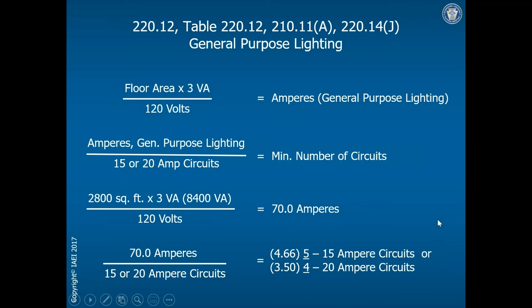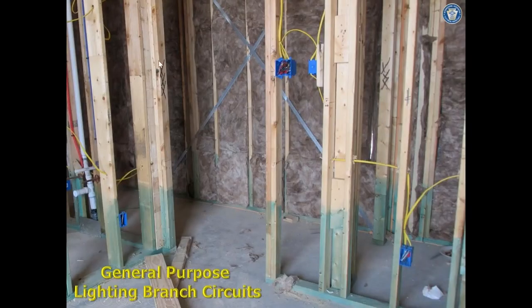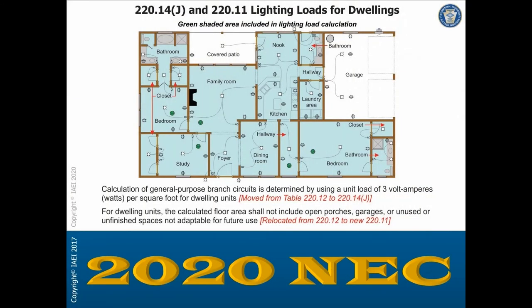This looks great on paper or for a test, but in the real world, a 3,400 square foot house with 2,800 square feet of living space would probably end up with around 10 general lighting circuits. By the time you factor in circuits for various lighting loads, receptacles, dishwashers, and everything else, you'd end up with more than five. Remember, the code is a minimum — the circuits running through bedrooms for lights and switches are your general lighting circuits.